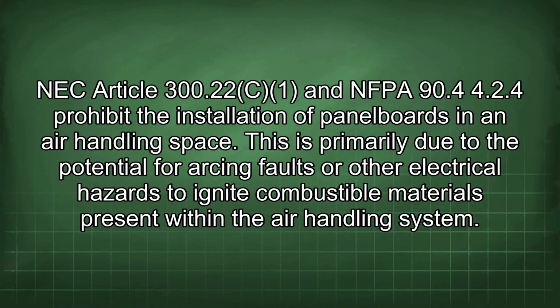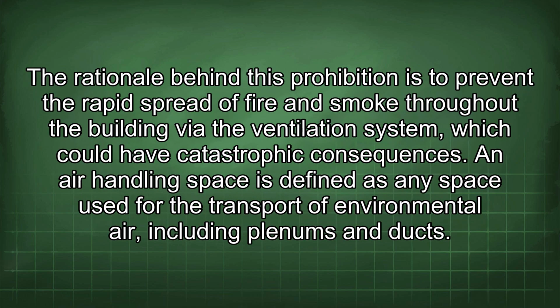NEC Article 300.22 and NFPA 90A, 4.4.2.4, prohibit the installation of panelboards in an air handling space. This is primarily due to the potential for arcing faults or other electrical hazards to ignite combustible materials present within the air handling system. The rationale behind this prohibition is to prevent the rapid spread of fire and smoke throughout the building via the ventilation system, which could have catastrophic consequences.